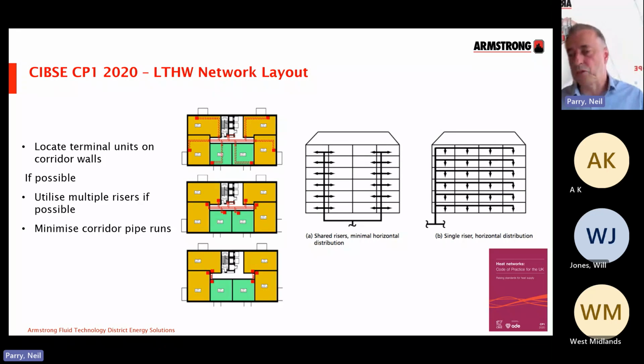you've got a single riser in the building and long lateral pipework. This is where, when you have that long lateral pipework, you have to keep that flow rate going around that network, and you are increasing the losses. Much better to have, say, two risers, much shorter lateral pipework, and then you don't need that constant circulation around the system, and you'll dramatically reduce the losses. I think it's roughly 65 to 75% of all your heat losses on the network come from that lateral pipework. So we need to make sure we optimize that pipework wherever possible.